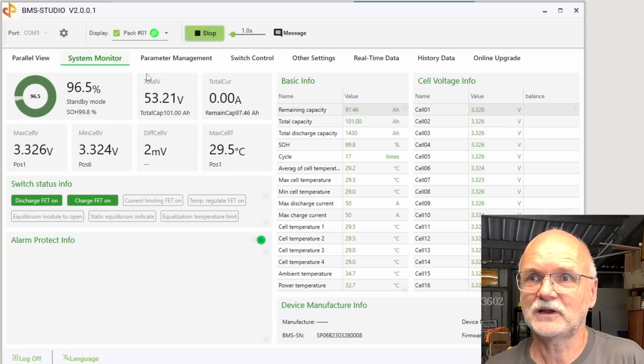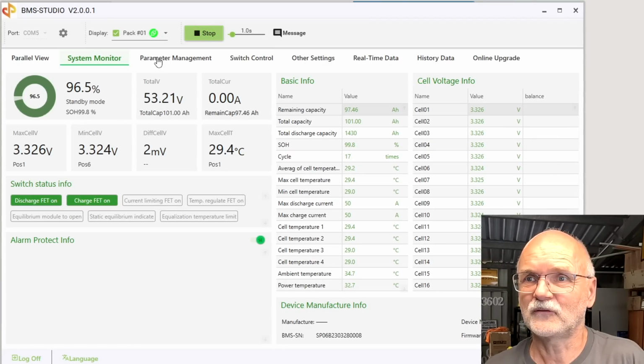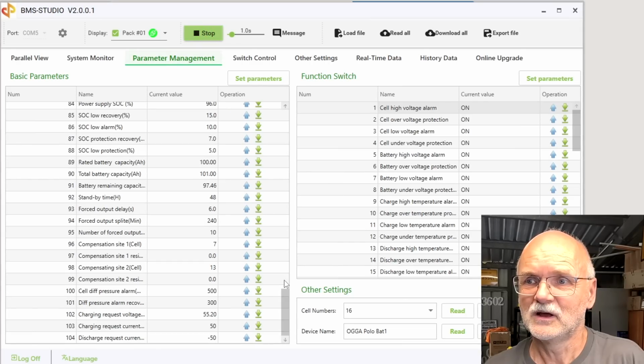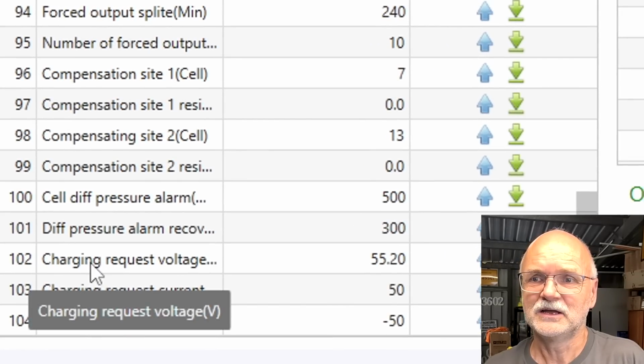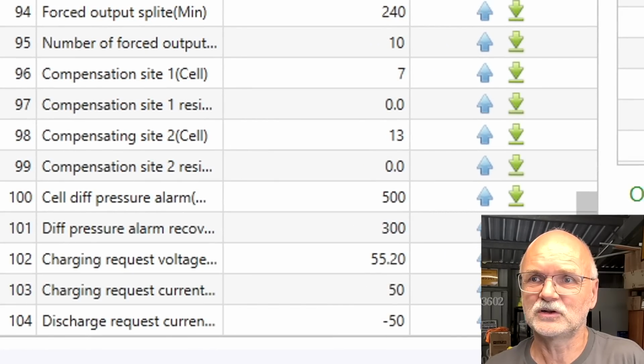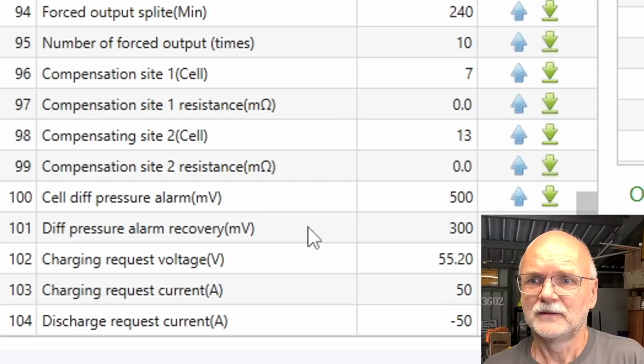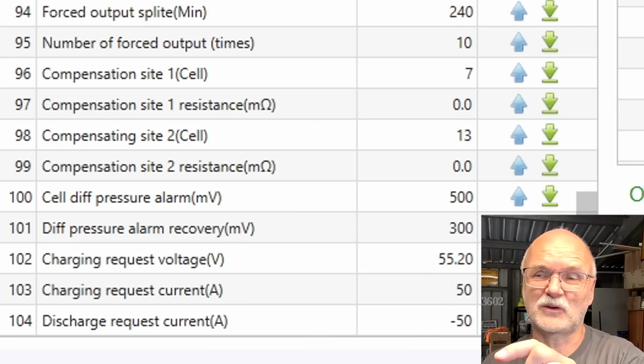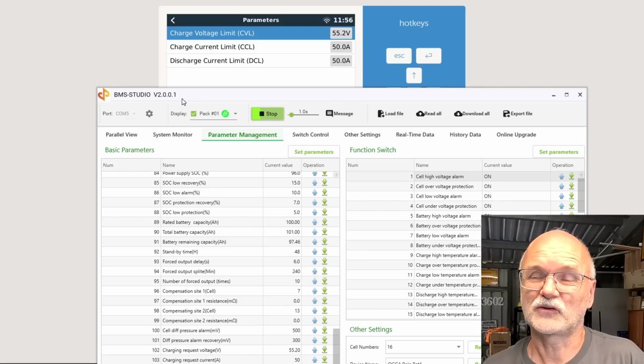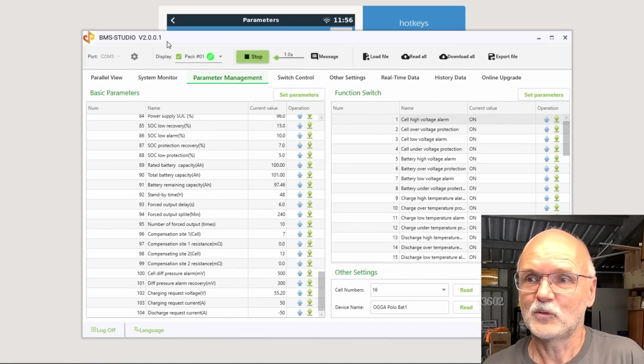Let's confirm this quickly. We go back into the software, parameter settings, all the way down, we can see here charge request voltage. There we go, 55.2 volts. Charge current 50 amps and discharge current negative 50 amps. So exactly what we request here from the BMS is also showing here in the Victron system. Communication is established, wonderful.